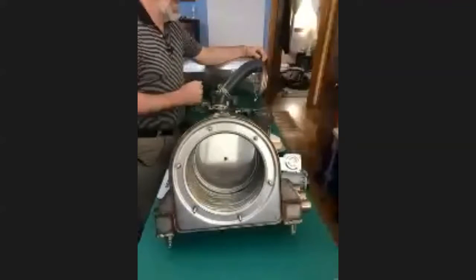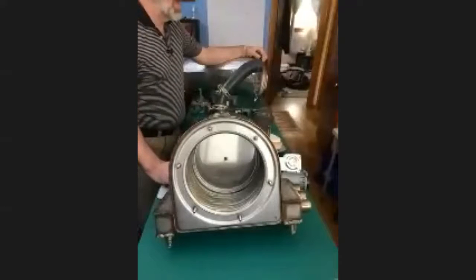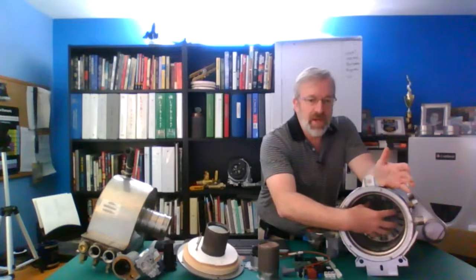Now, as we move back over to the fire tube style, right here, this is your fire tube style. It's a little bit different. We fire down through the combustion chamber there. As we clean this one, we clean it up with a little bit of vinegar and water solution, then clean it with a green scrubby, and then rinse down through. So this style of heat exchanger is a little bit easier to clean.